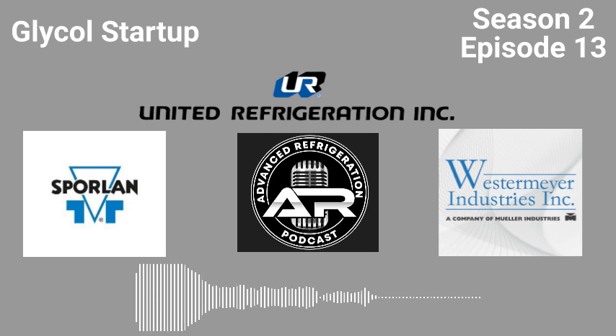You got all the air bled out of the rack, because when you start charging this, you're going to be going into your liquid line. You're not giving it a full liquid charge, but you're going to be charging through the liquid line and pumping it down into the rack. So as you're doing this, you want to make sure you have full flow, your flow switches work, and your delta pressure is good. Whatever the store calls for, if it's 10 pounds, 15 pounds, 20 pounds, make sure that's all good. And then you want to start charging the rack.